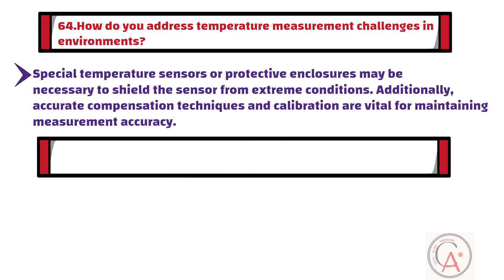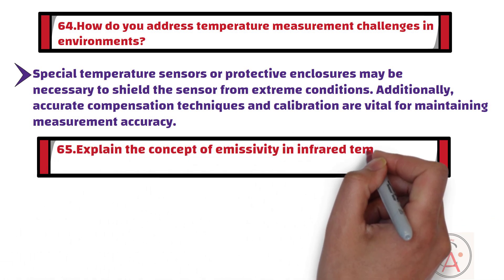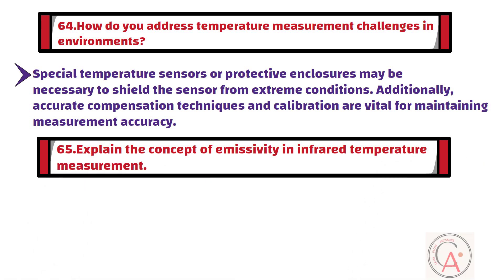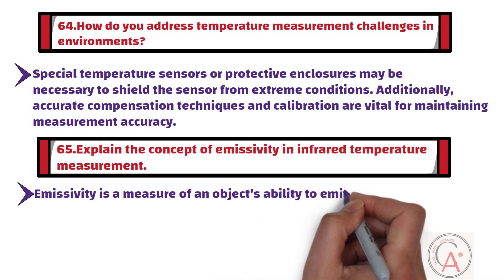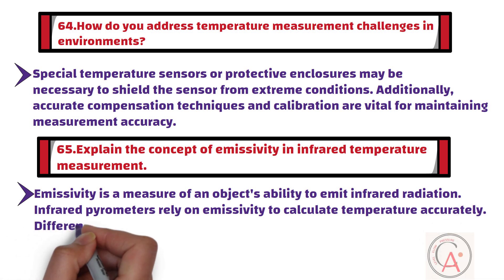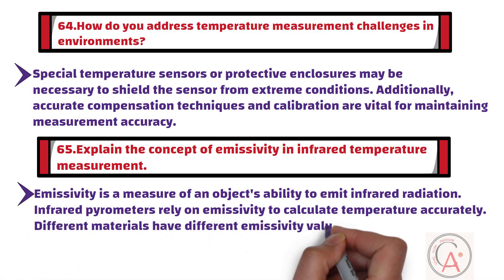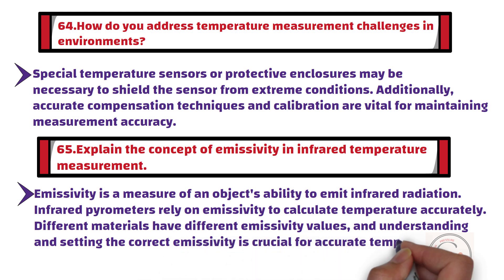Question number 65: Explain the concept of emissivity in infrared temperature measurement. Emissivity is a measure of an object's ability to emit infrared radiation. Infrared pyrometers rely on emissivity to calculate temperature accurately. Different materials have different emissivity values, and understanding and setting the correct emissivity is crucial for accurate temperature measurement.